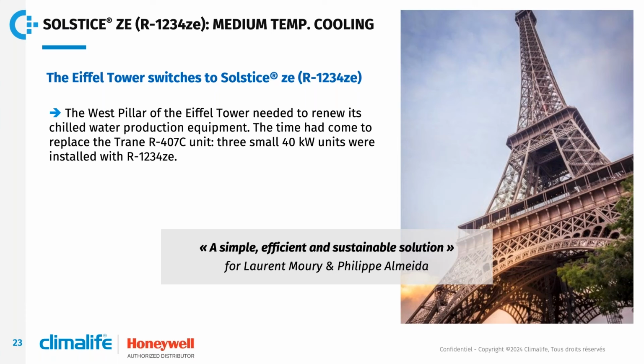In fact, the west pillar of the Eiffel Tower needed to renew its chilled water production equipment, having roughly 120 kilowatts. It was an old Trane chiller, and it was time to renew this installation. After reflection, the solution carried out here was to use three small units of 40 kilowatts each, using R1234ze as an ultra-low GWP solution. As a result, as you see here, the solution was very simple, efficient, and sustainable.